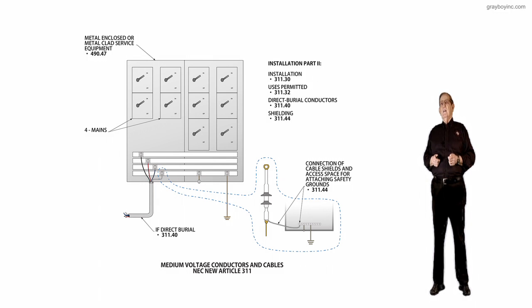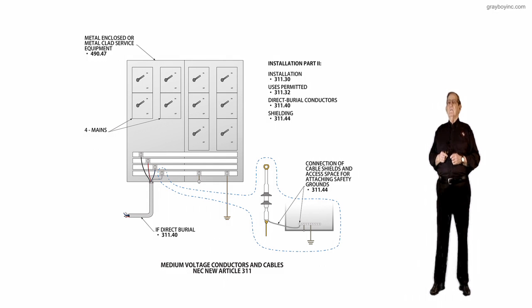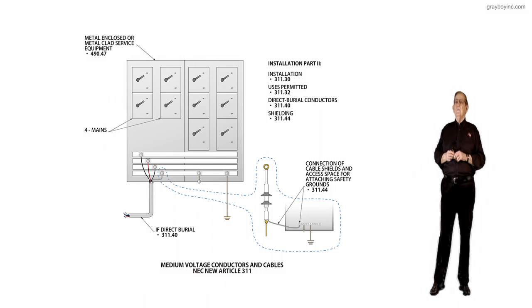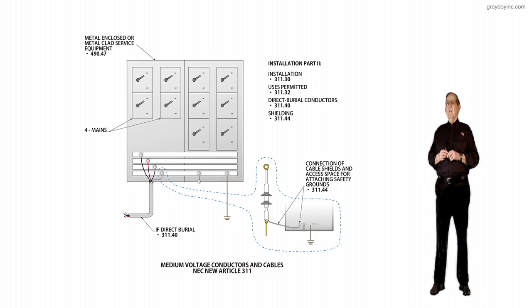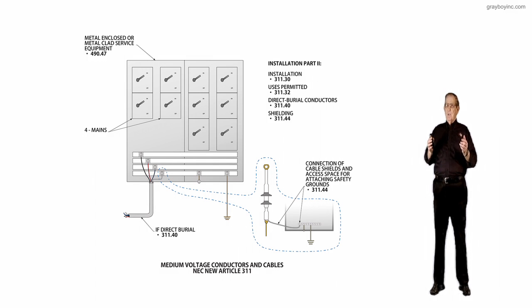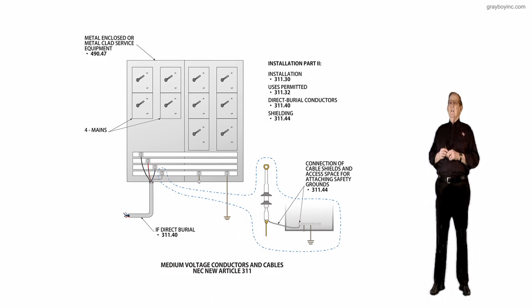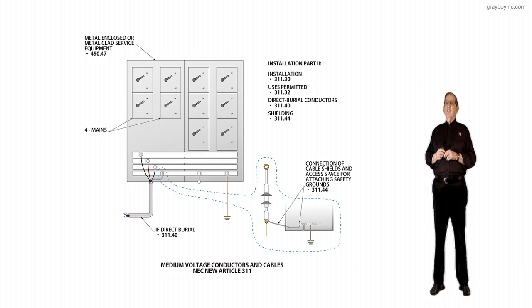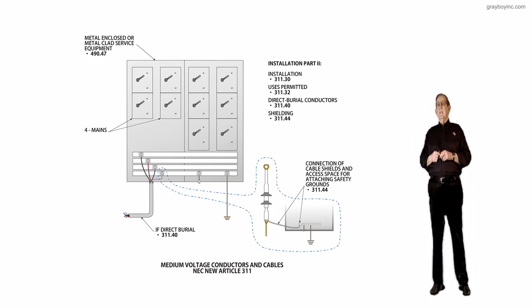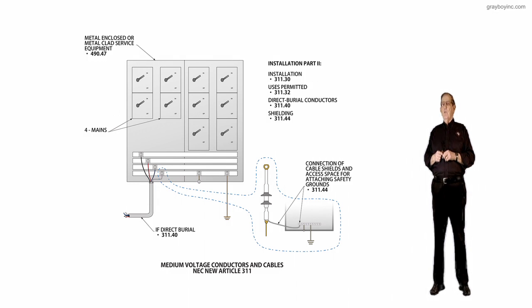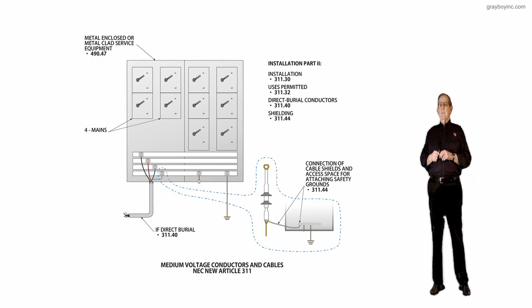To review what this Part II applies to: installation is 311.30, use permitted where you can use this article is 311.32, direct buried conductors is in 311.40 by the NEC rule now, and shielding is 311.44. The connection of cable shields, access space, and attaching safety grounds is also covered in 311.44, as you see in the illustration, pointing to the shielding that would take place to handle the stress buildup from the high voltage.